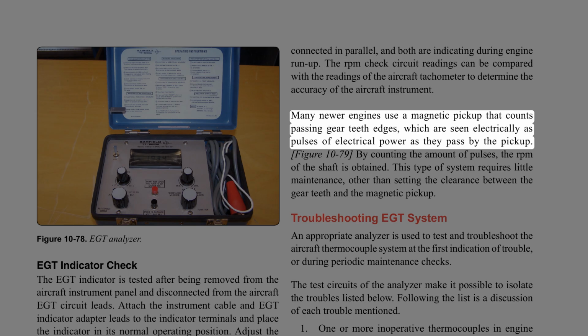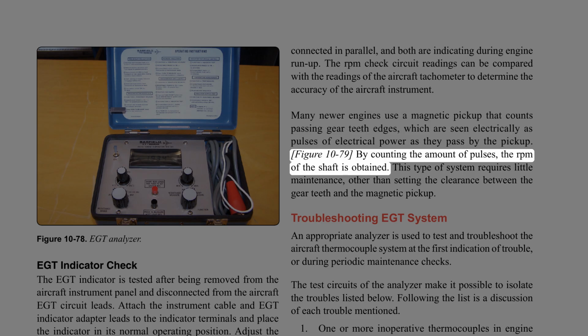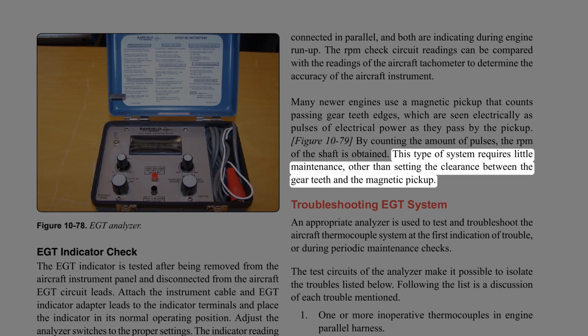Many newer engines use a magnetic pickup that counts passing gear teeth edges, which are seen electrically as pulses of electrical power as they pass by the pickup. Figure 10-79. By counting the amount of pulses, the RPM of the shaft is obtained. This type of system requires little maintenance, other than setting the clearance between the gear teeth and the magnetic pickup.